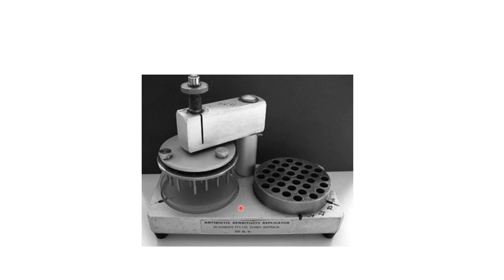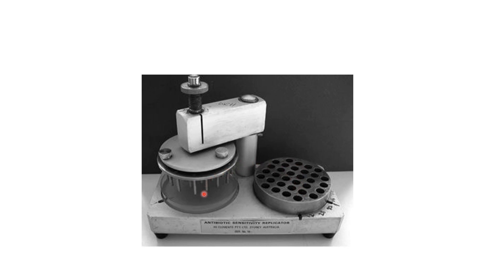This equipment is called a multiple inoculator or Steer's replicator. In agar dilution, multiple strains can be inoculated on Mueller Hinton agar of different antibiotic concentrations for calculating the MIC. This device has wells — each well contains a different type of strain or microorganism — and a probe. When the probe is dipped into the wells, organisms are transferred and can be inoculated onto Mueller Hinton agar in one step.